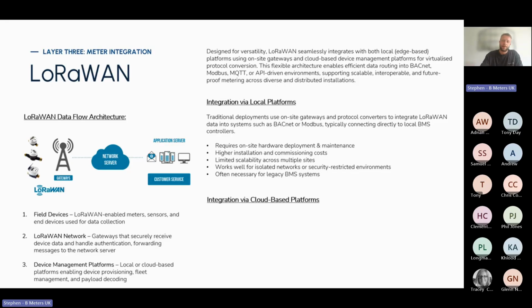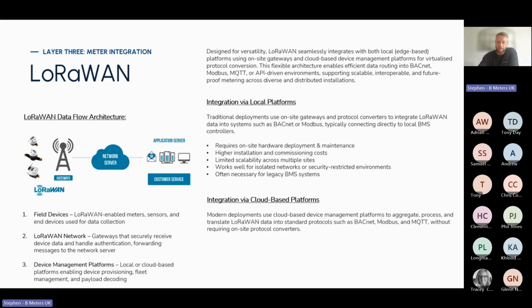and then you utilize the BACnet or Modbus conversion from there. Now, integration via cloud-based platforms is a more modern adjustment. Modern deployments will use cloud-based device management platforms to aggregate, process, and translate LoRaWAN data into standard protocols such as BACnet, Modbus, and MQTT without requiring on-site protocol converters. So in this sense, you would have an online platform where you onboard all your devices, gateways, and sensors, and when the hardware is on site, it's all managed by the cloud-based platform. So the device sensor will jump to the closest gateway.